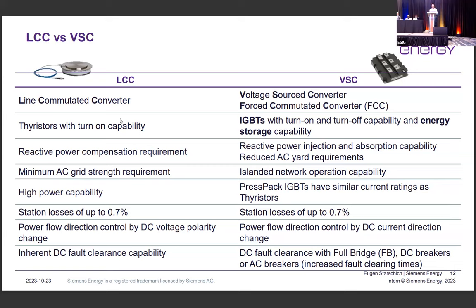One point you will not find here is the costs. We weren't comparing the costs, because cost highly depends on the existing network configuration. I think the big advantage of the VSC is that it's capable of operating in very, very weak networks or even islanded networks, which is not possible for the LCC. For the LCC, we require a high short circuit ratio, that means the ratio between the power of the HVDC station and the available short circuit power of the network. So if we consider the network enhancement for the LCC technology, this usually flips the coin. In most cases, VSC technology is cheaper, because it can be easily integrated in the network.